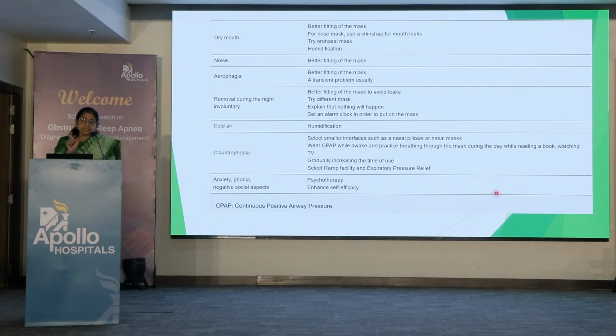So when we do a titration study, we put exactly the pressure that is required. Even in a CPAP machine, we have limits, a lower limit and an upper limit. Suppose your sleep study showed that the mean titration pressure required is, say, 10, and the maximum pressure required is 12. We can set the machine with the lower limit at 8 and the upper limit at 12, so that even though the CPAP is fluctuating, it will give only that much fluctuation and remain more or less in that range.